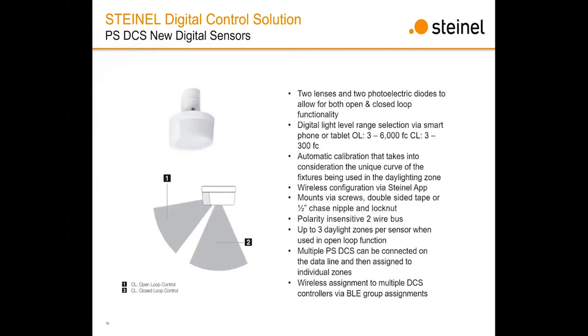And because in several situations you don't need a sensor where you need a photo cell, or vice versa, we do have our digital photo cell. A couple of unique things about this: it can be open loop or closed loop, and we commission that right in our app. You can do up to 3 daylighting zones with just a single photo cell. Many of our competitors will require a photo cell in every single one of those zones. With our DCS and our photo cell, you only need a single photo cell. So all of this adds up to fewer components to install in the field, easier wiring and easier installation.